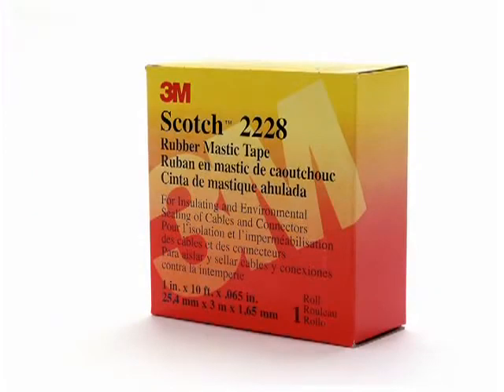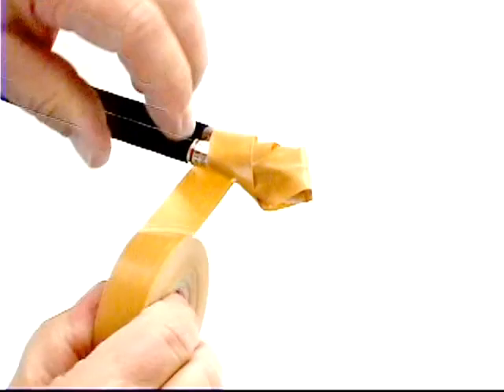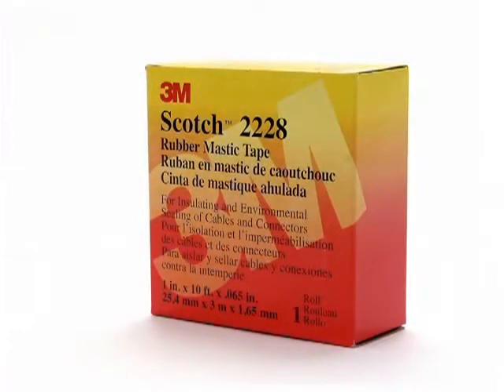If you need rapid, clean reentry to the connection, wrap it with two half-lapped layers of varnished cambric tape. In the example we are about to show you, we're assuming that reentry is not important, so this step is not shown.